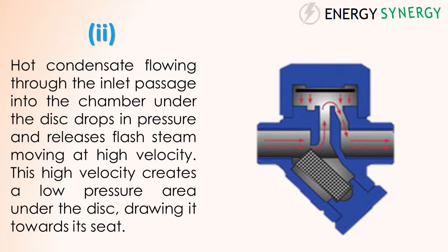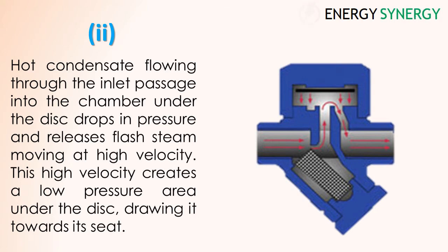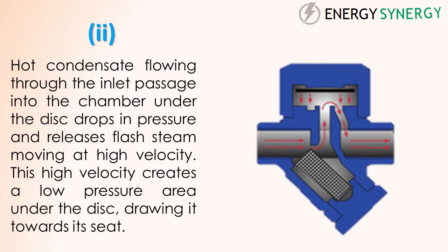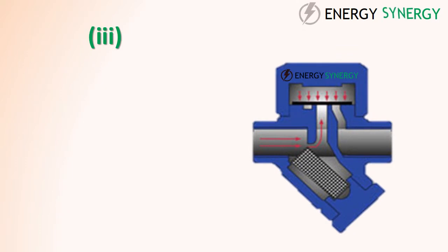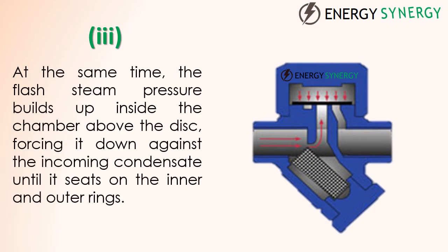Stage two: hot condensate flowing through the inlet passage into the chamber under the disc drops in pressure and releases flash steam moving at high velocity. This high velocity creates a low pressure area under the disc, drawing it towards the seat. At the same time, flash steam pressure builds up inside the chamber above the disc, forcing it down.